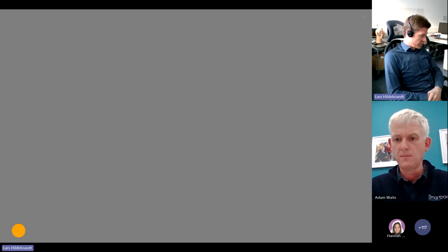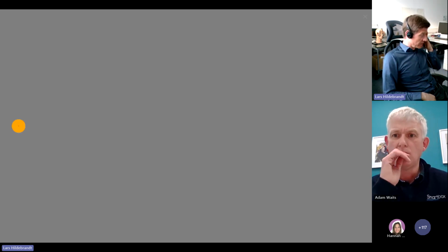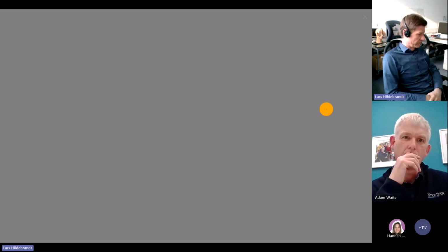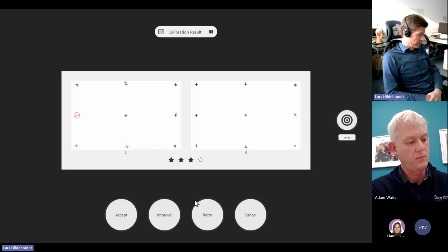For any calibration that you do, first of all, our calibration is forgiving. That means I'm now looking away. You see the screen, it waits for me, and after some time I return and I continue. I can even close one eye when I look at the screen. That means it waits for 2 eyes usually, but after some time, it skips this location and continues with just 1 eye. This is extremely helpful if you have users that tend to rotate the head towards corners of the screen where 1 eye is not visible.